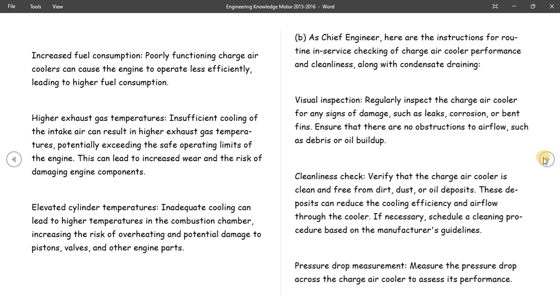Ensure that there is no obstruction to airflow, such as debris or oil build up. So first of all, the first thing you must do is a visual inspection. The second step is cleanliness. Verify that the charge air cooler is clean and free from dirt. After doing the visual inspection, ensure that the air vents and the coolers are free from dirt and dust.